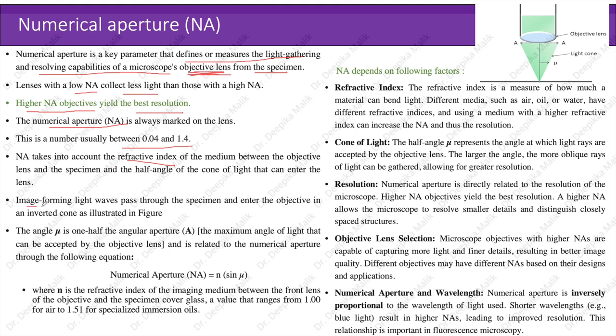Image-forming light waves pass through the specimen and enter the objective in an inverted cone. The angle nu is one half the angular aperture, denoted by A — the maximum angle of light that can be accepted by the objective lens. Numerical aperture is given by: NA = n × sin(nu), where n is the refractive index of the imaging medium between the front lens of the objective and the specimen cover glass, ranging from 1 for air to 1.51 for specialized immersion oils. The refractive index measures how much a material can bend light; using a medium with a higher refractive index increases the numerical aperture and thus the resolution.